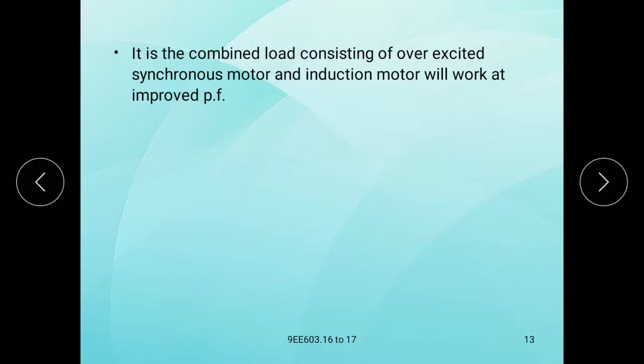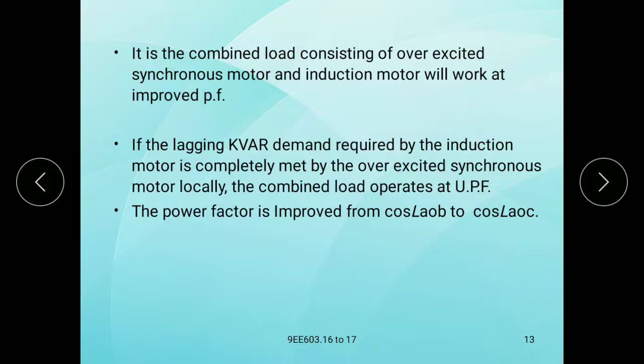If the lagging KVAR demand required by the induction motor is completely met by the overexcited synchronous motor locally, the combined load operates at UPF, unity power factor. The power factor is improved from cos AOB to cos AOC.